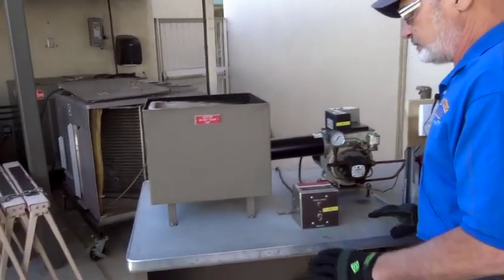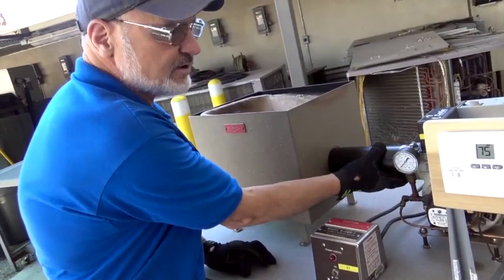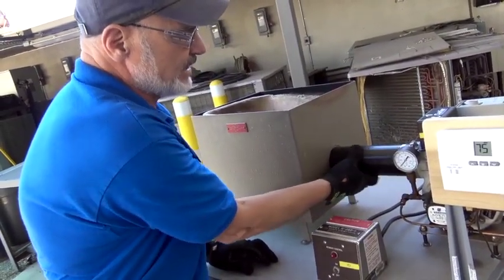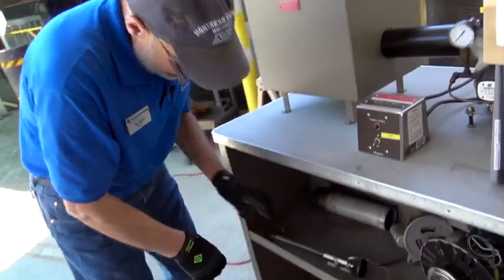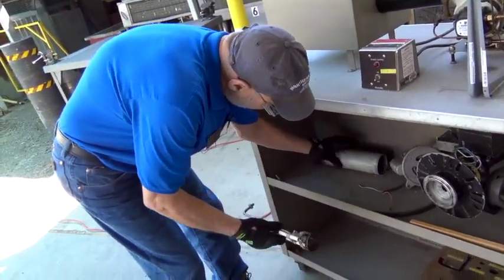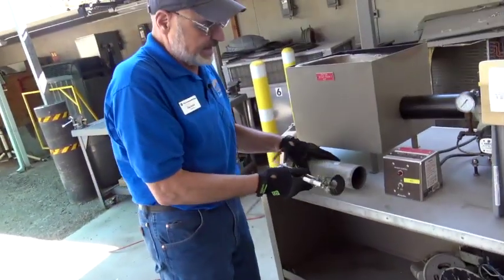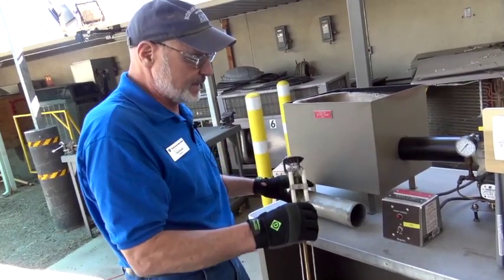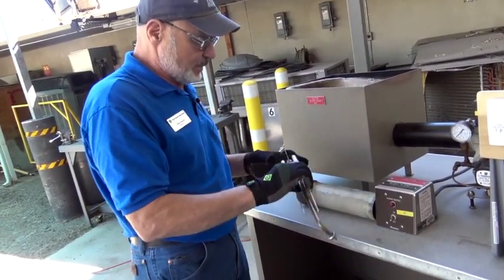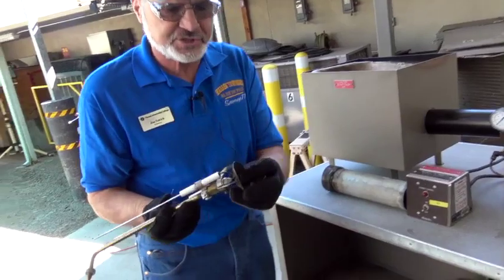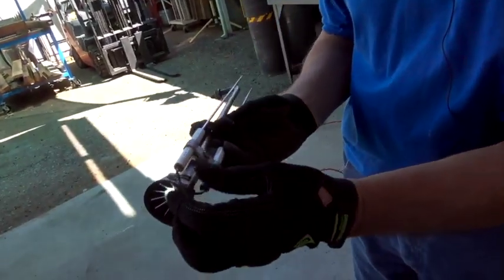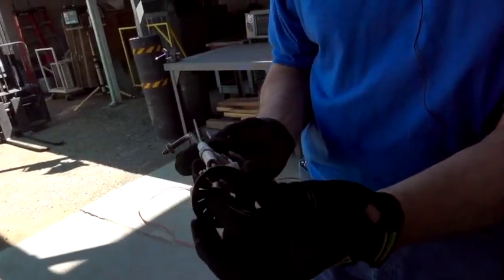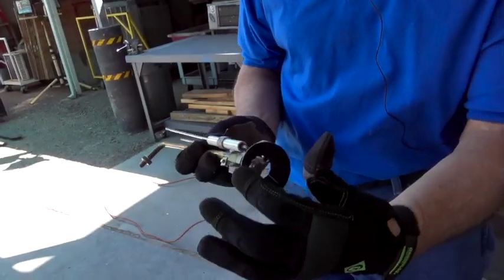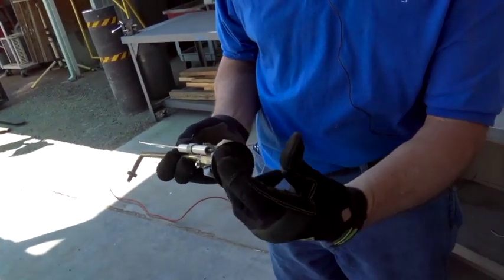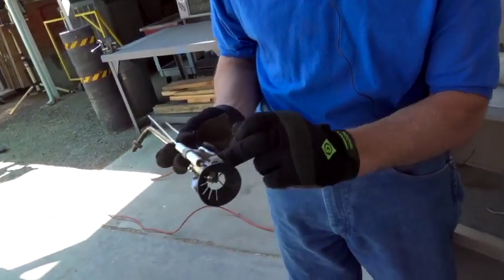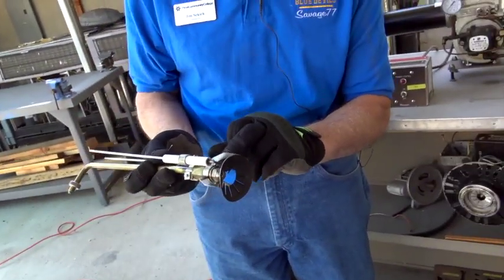Now over here, this is our combustion air tube. It's a new part here. I'll show you the one we pulled out that was bad. It comes as a whole complete kit. As you can see, we had some issues with our retention ring here. It was pretty warped. Real bad condition. And that retention ring acts as an atomizer with the fuel nozzle.